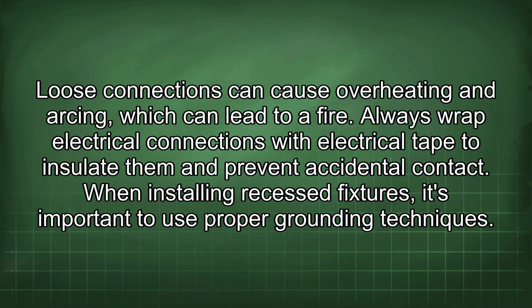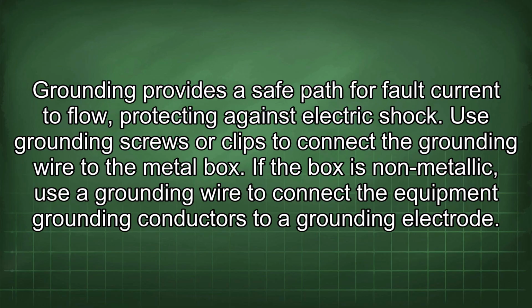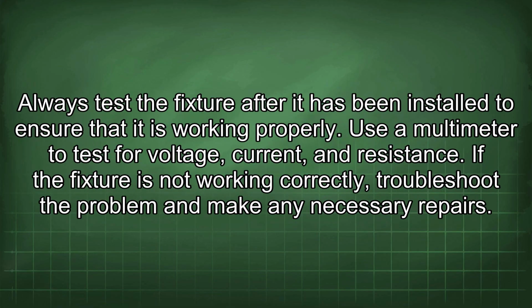When installing recessed fixtures, it's important to use proper grounding techniques. Grounding provides a safe path for fault current to flow, protecting against electric shock. Use grounding screws or clips to connect the grounding wire to the metal box. If the box is non-metallic, use a grounding wire to connect the equipment grounding conductors to a grounding electrode. Always test the fixture after it has been installed to ensure that it is working properly. Use a multimeter to test for voltage, current, and resistance. If the fixture is not working correctly, troubleshoot the problem and make any necessary repairs.